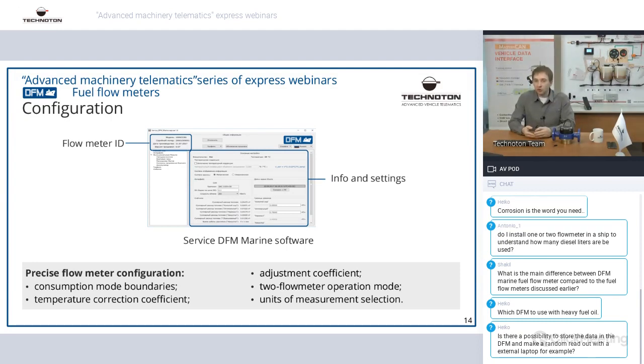We also can apply a correcting coefficient. For example, if we install the flow meter on a diesel generator and we see that we are not getting accurate fuel consumption information, let's say we're getting 97%, and you just keep in your head, I have a 3% error. Please don't panic. Ask your sales manager, ask our technical team. We'll assist you with how that error can be corrected, either using settings inside of the flow meter, or using additional mechanical ways, using some additional filters or fittings, to lower the inaccuracy error. So please know that it's quite important.